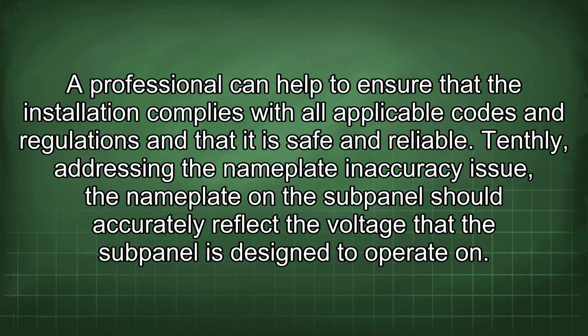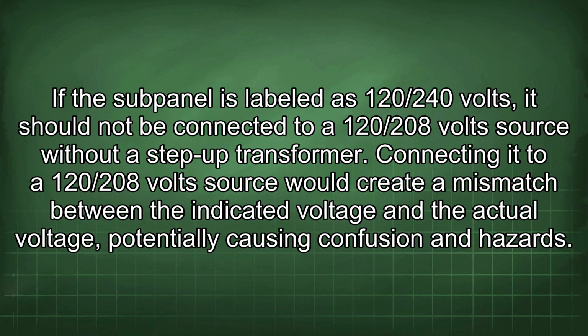Tenthly, addressing the nameplate inaccuracy issue. The nameplate on the subpanel should accurately reflect the voltage that the subpanel is designed to operate on. If the subpanel is labeled as 120/240 volts, it should not be connected to a 120/208 volt source without a step-up transformer. Connecting it to a 120/208 volt source would create a mismatch between the indicated voltage and the actual voltage, potentially causing confusion and hazards.